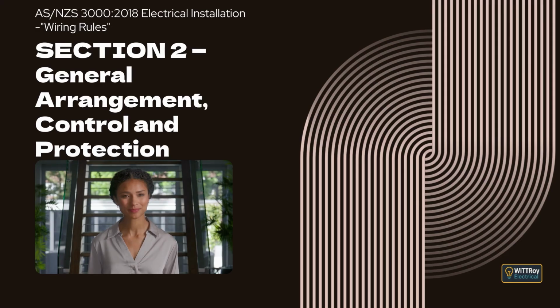For residential installations, no more than 3 final subcircuits may be on one RCD. If there is more than one final subcircuit, at least 2 RCDs must be installed. These rules make sure that one tripping device does not shut down the entire home or building.